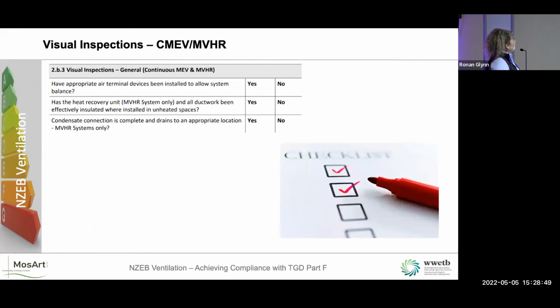For CMEV and MVHR then, is the system balanced? Do we have the connected ductwork insulated in the right place, especially in unheated spaces? Is the condensate drain there? The condensate connection is complete and drains to an appropriate location. Okay, so there's no point in having a condensate drain there if it's not going to an appropriate location.